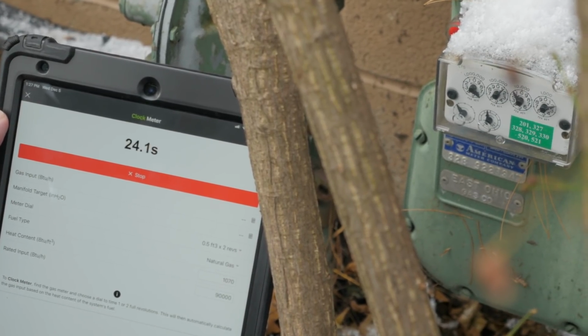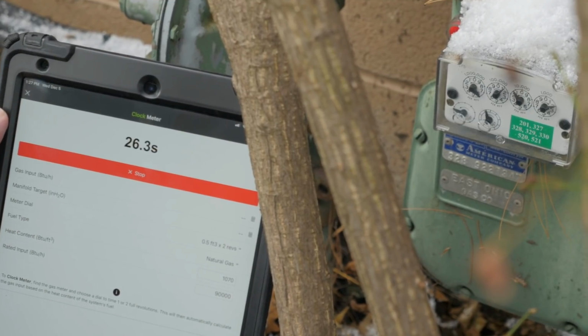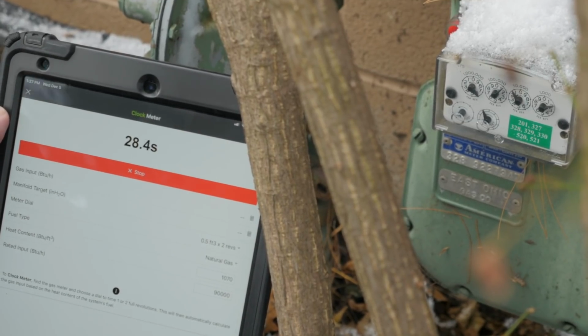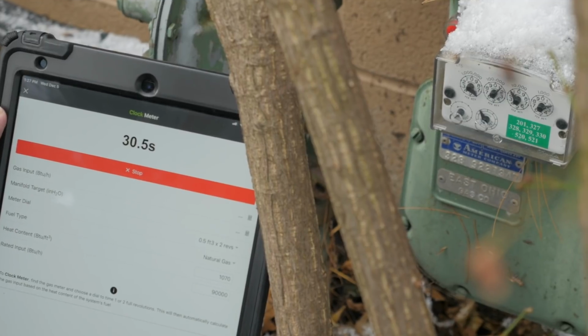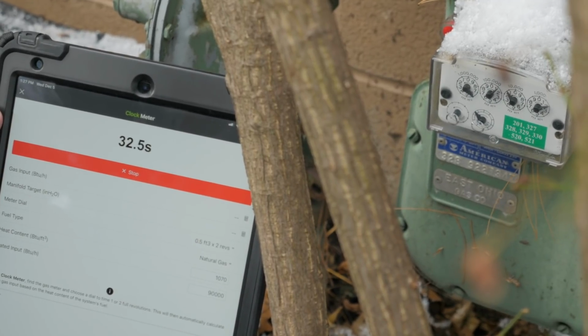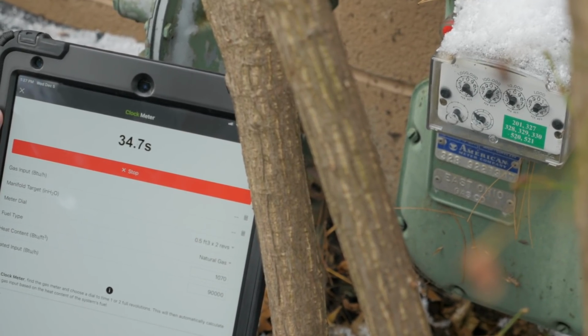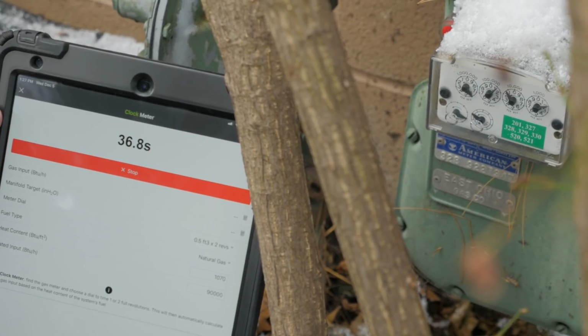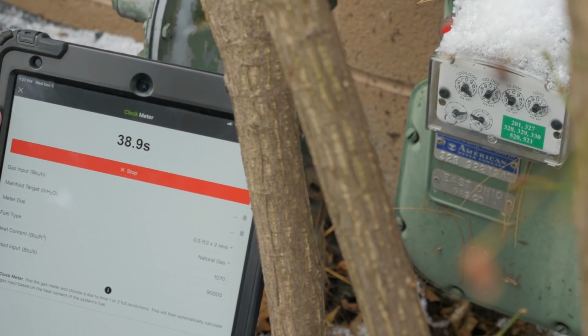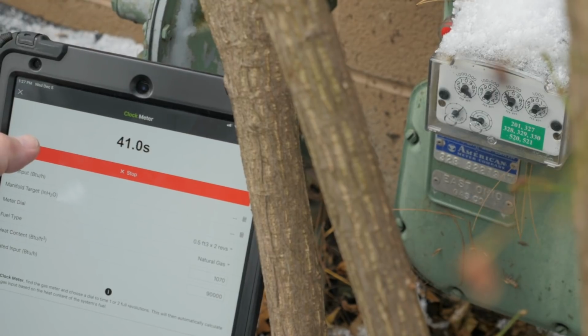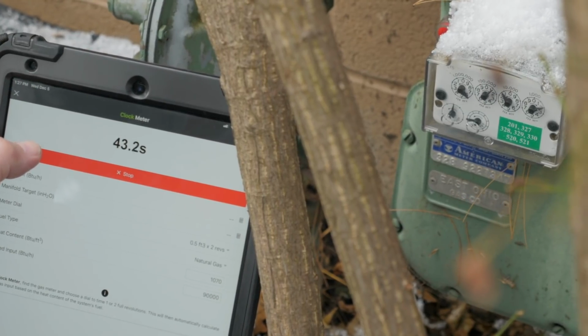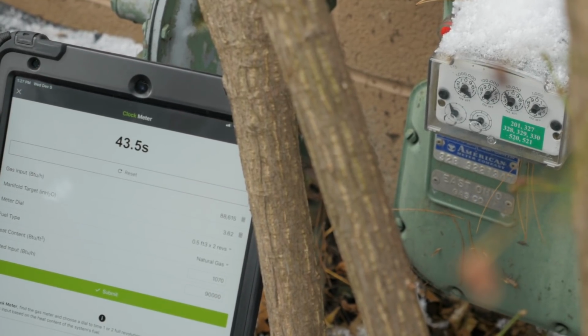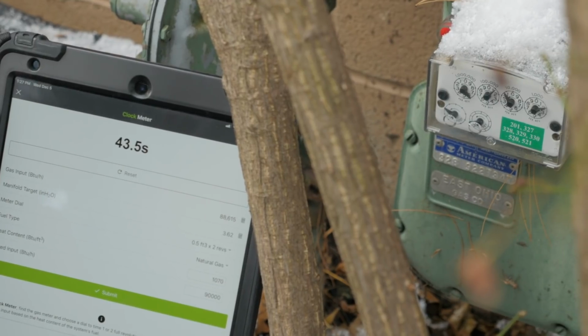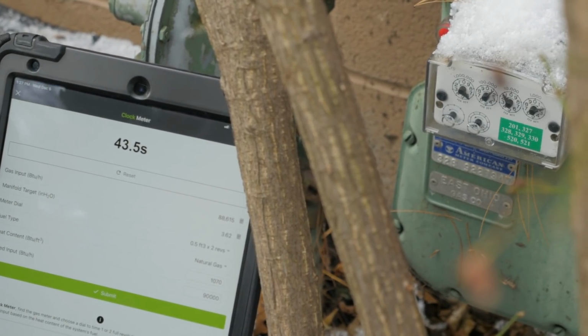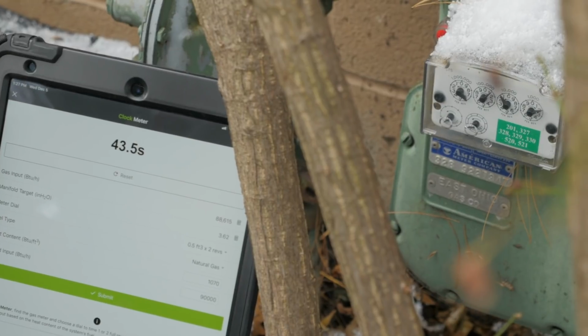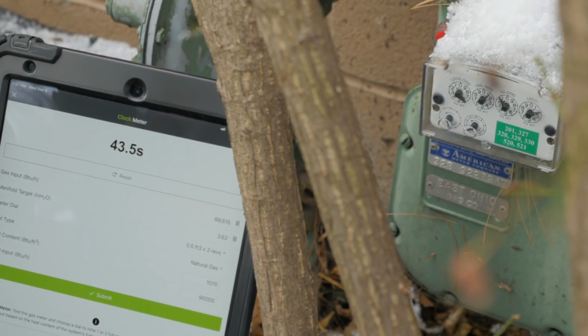We need to let this go around 2 times here, so it's gone around once and let it go around 1 more time. What this is doing is we're clocking the gas meter, determining how much gas is going through that meter so that we know where to set our fuel pressure on our furnace, because again, it's a nominal 3.5 inches of water column. We're just about at the top here, so mark. All right, so it's telling us right now that our current input is 88,615. We need to set that gas pressure to 3.62 inches. So let's go back inside and get that reset.